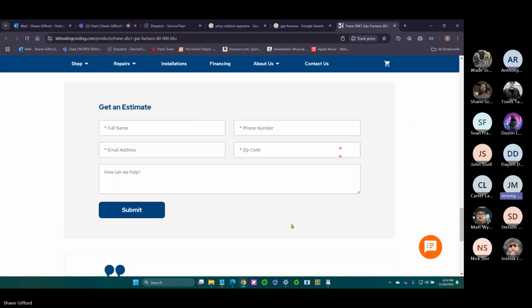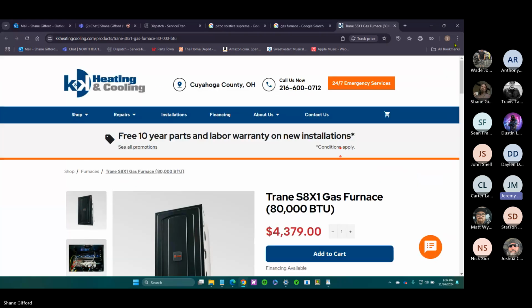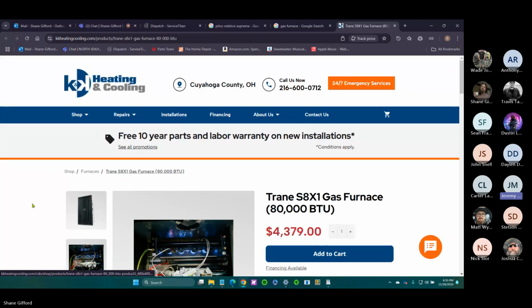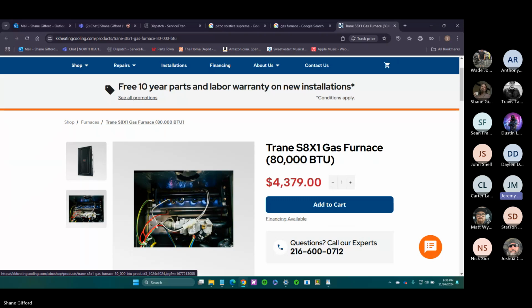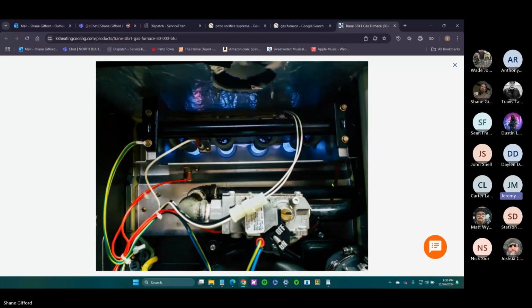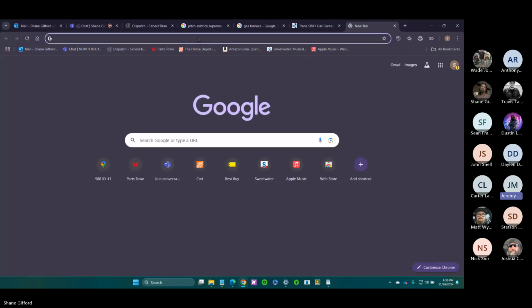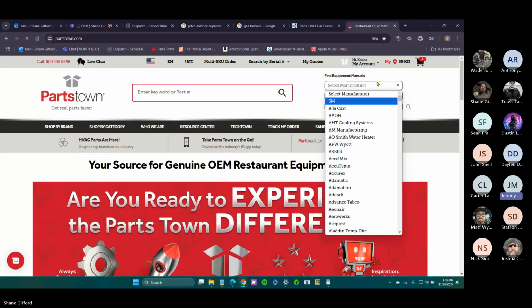I've had a lot with Five Guys, their temperature probes going out. That's actually why I was looking at that Cooper Atkins, because I didn't realize the Fieldpiece K type is only rated for up to, I think, 260 or 280. I think on Amazon, that's what it says in the literature for those Fieldpiece ones. I had just been dunking that thing in oil, like when my high limits trip, I'd wonder if my high limits tripped. Oh yep, it tripped, it's like 425. It reads, but it's a good thing you told me that, because it's probably breaking down that thermistor or thermocouple like nobody's business.